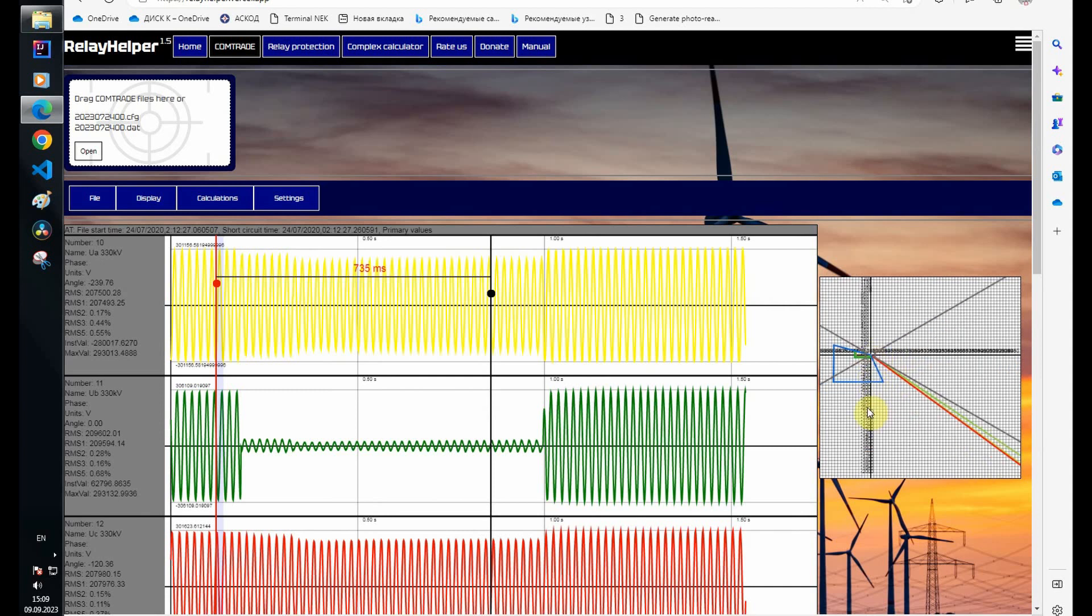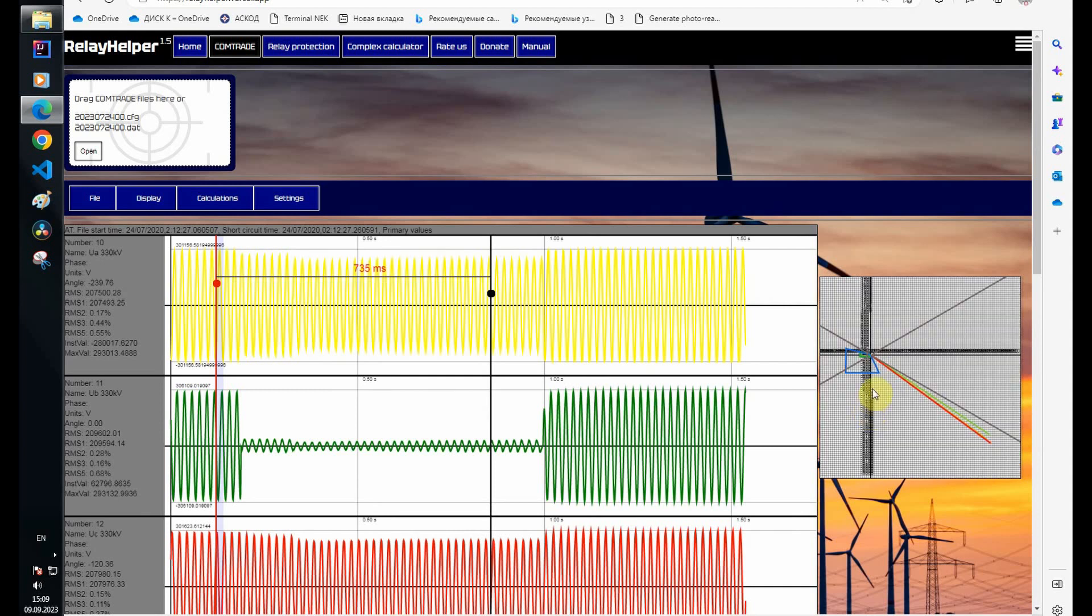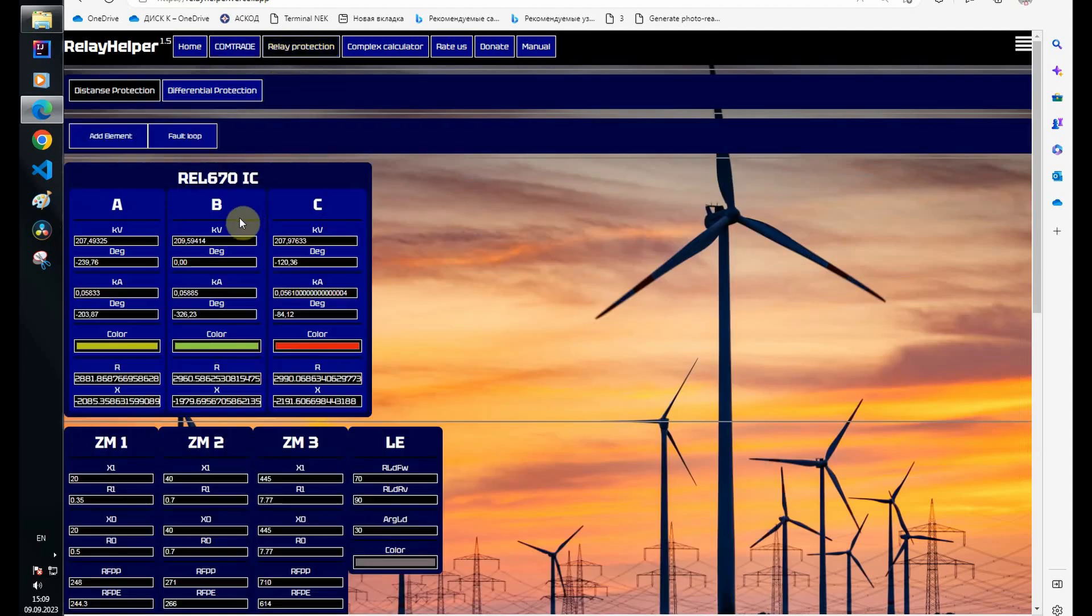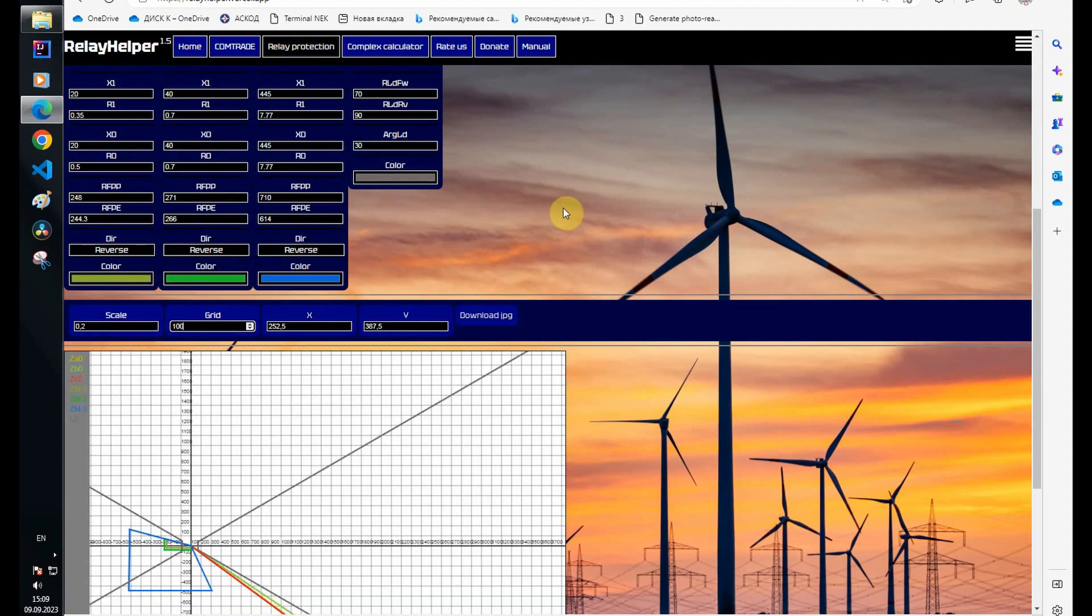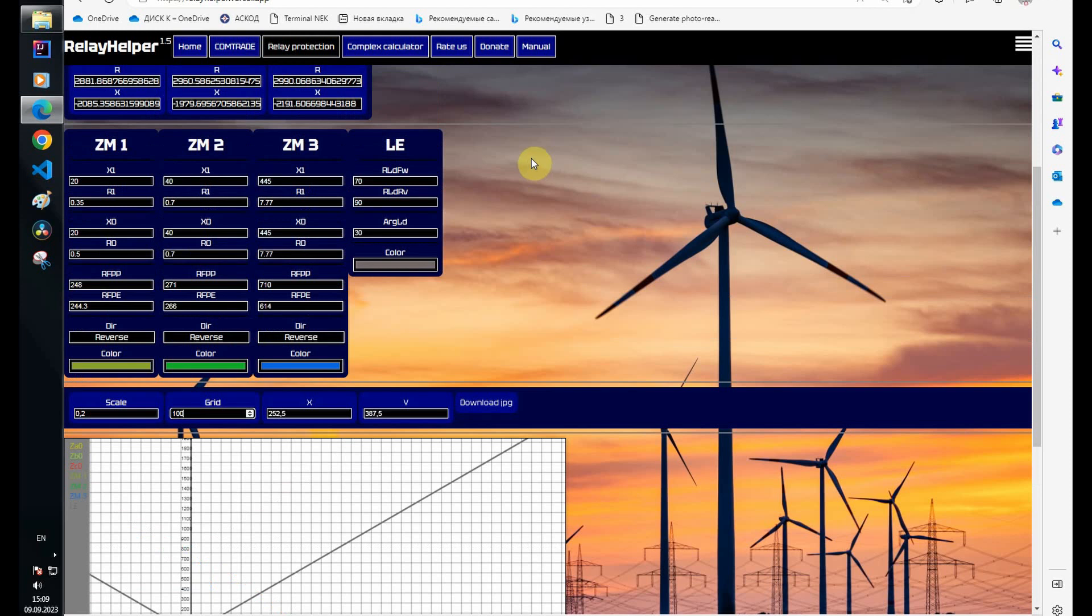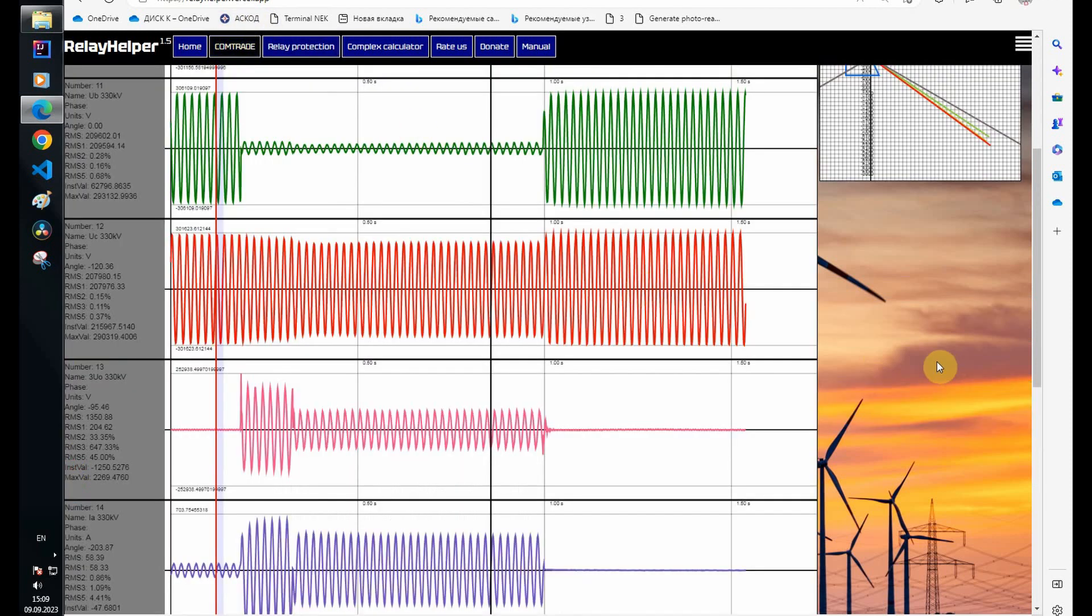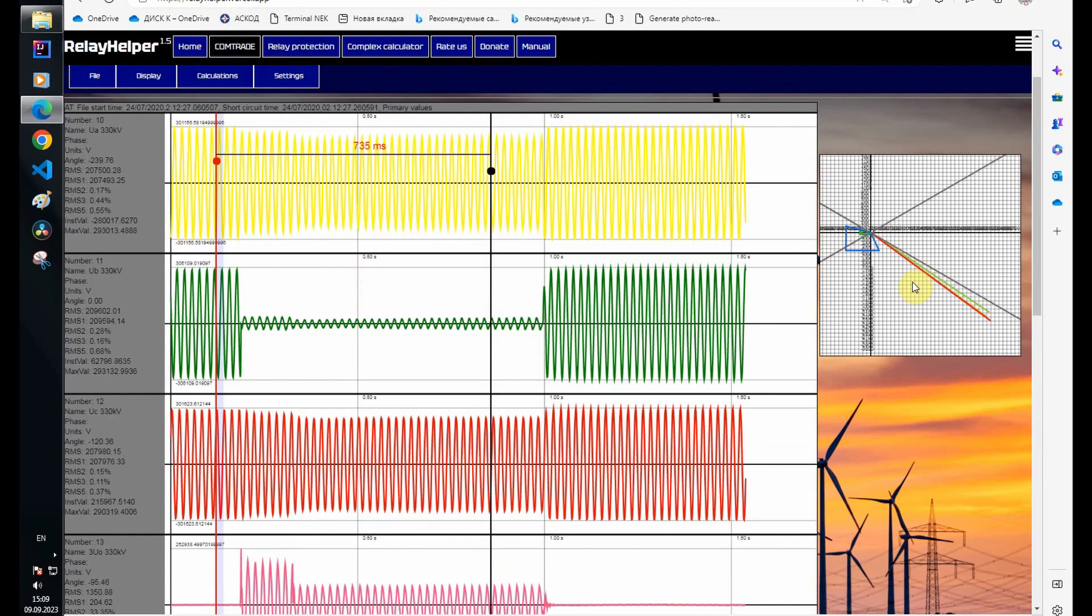Pay attention to one thing. I need to increase the grid step further. Look at the load angle before the fault. It does not fit within the 30 degrees setting in the device. This often happens in Ukraine now. The load angle is very big and this makes it difficult to set up protection zones.